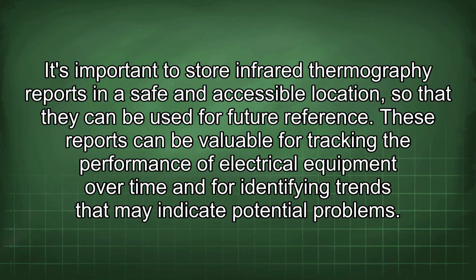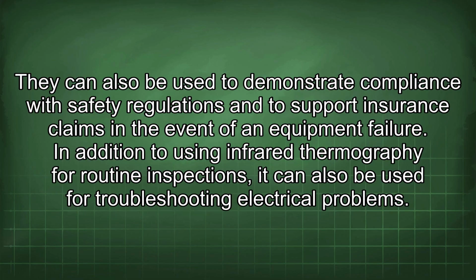It's important to store infrared thermography reports in a safe and accessible location so that they can be used for future reference. These reports can be valuable for tracking the performance of electrical equipment over time and for identifying trends that may indicate potential problems. They can also be used to demonstrate compliance with safety regulations and to support insurance claims in the event of an equipment failure.